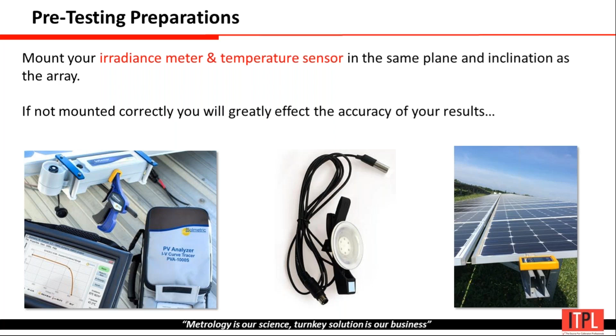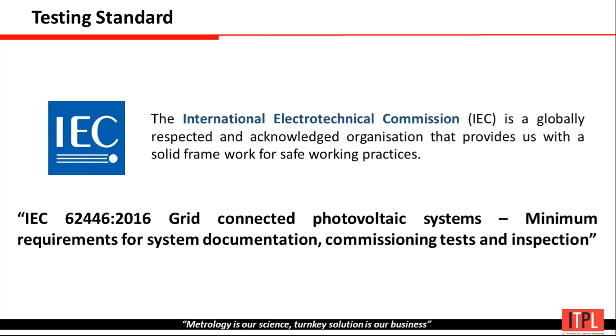As we all know, IEC standards are the main thing, which every piece of testing equipment follows. So if you are talking about IV testing or solar power plant testing, there are IEC 62446 and a few more standards like IEC 61829, then IEC 60891. These are a few standards related to the photovoltaic system, whether it's grid connected or STC converted. So these are the standards we are following in the instrument exactly.